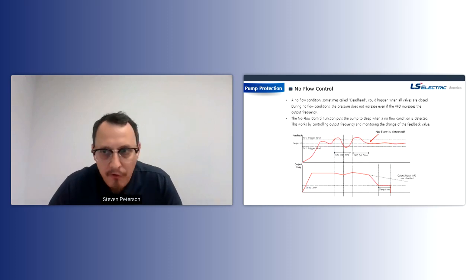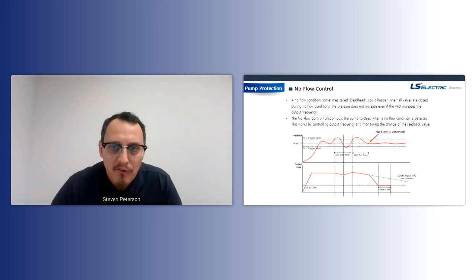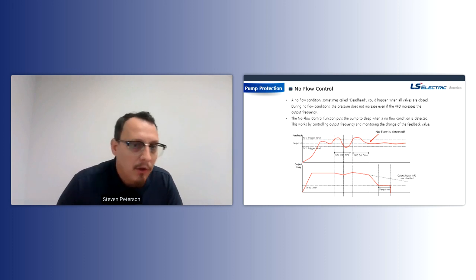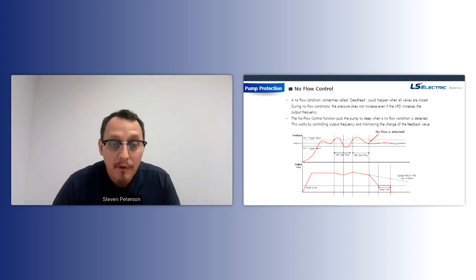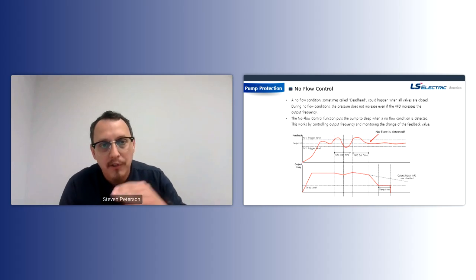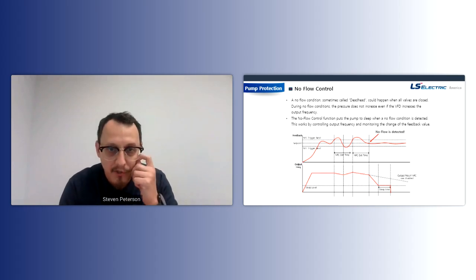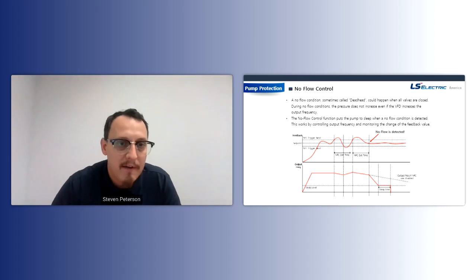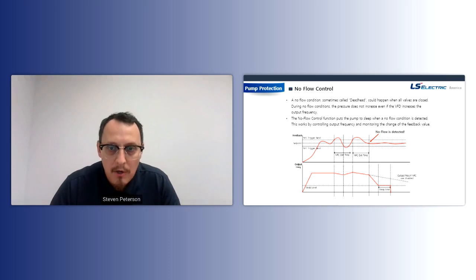This is one of my favorite functions. We didn't have it on the previous generation, but we've added it to the H100 Plus. This is no flow control. So you close a valve and the pump goes to a deadhead situation. This could happen when all the valves are closed. So there's no flow, but the pressure isn't increasing enough to lower the output frequency. So the drive effectively never goes to sleep, or sleep takes a really long time to occur. That could be an issue. The pump's just heating up.